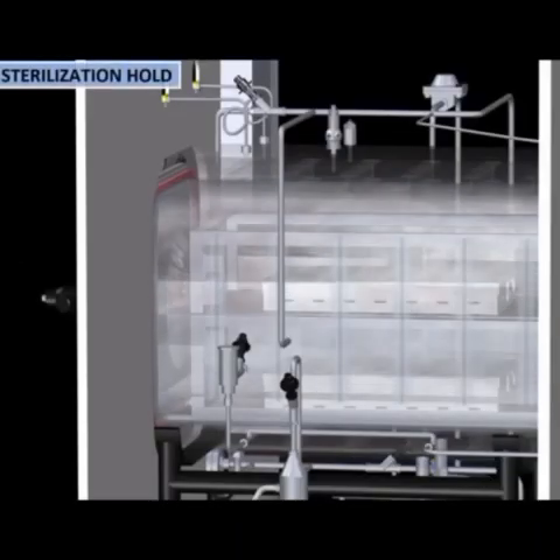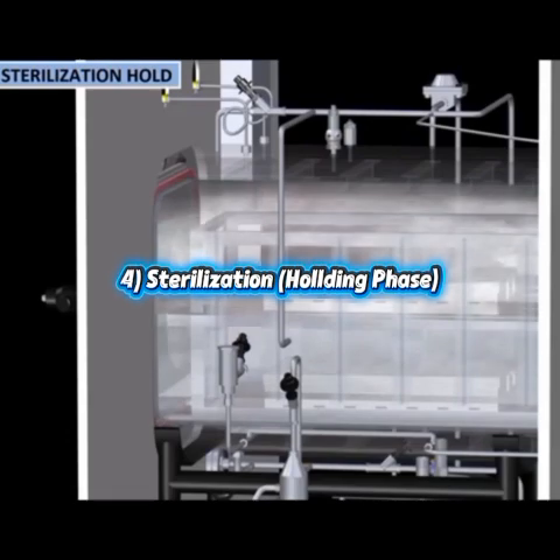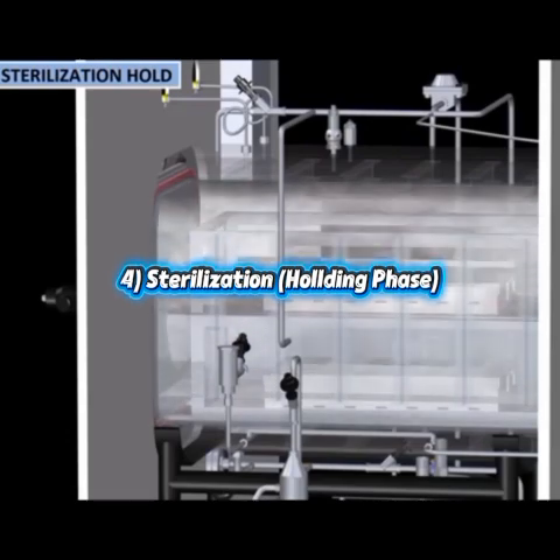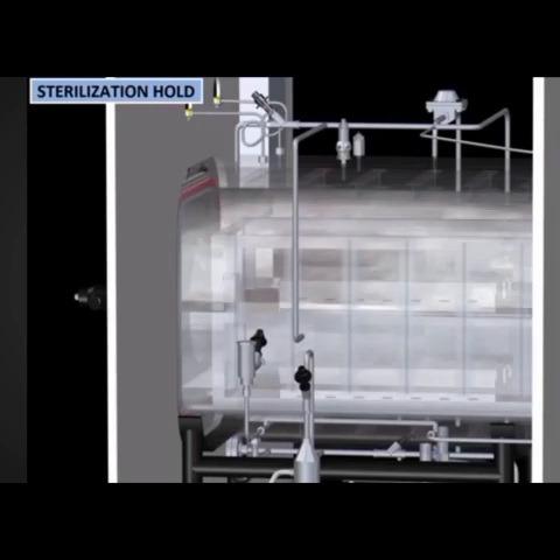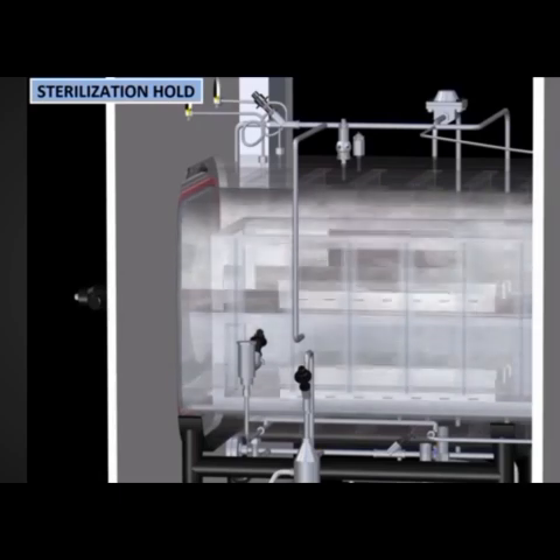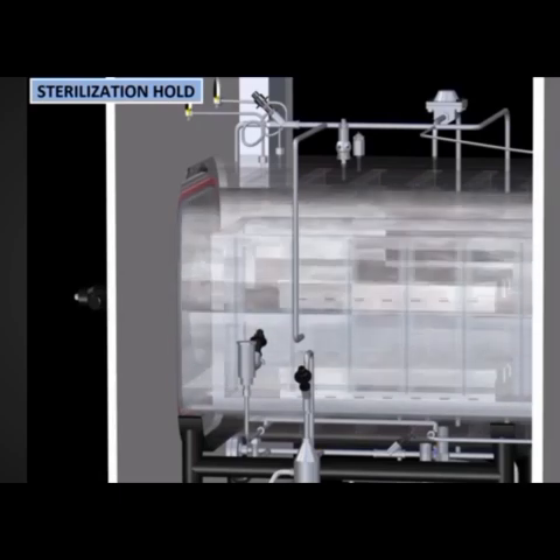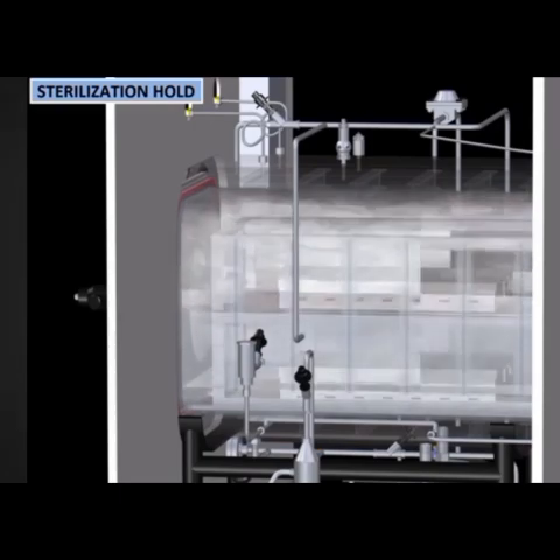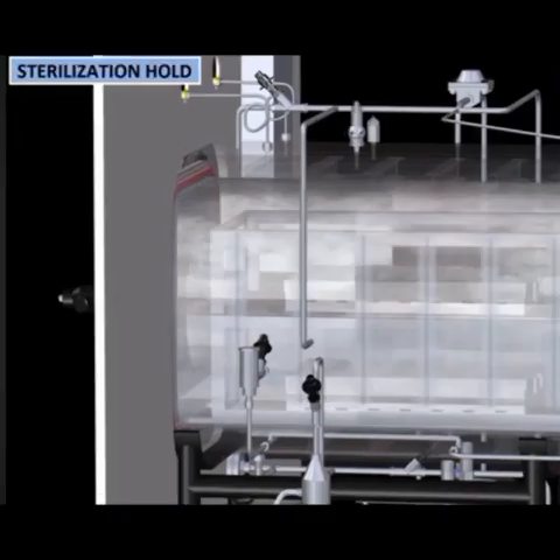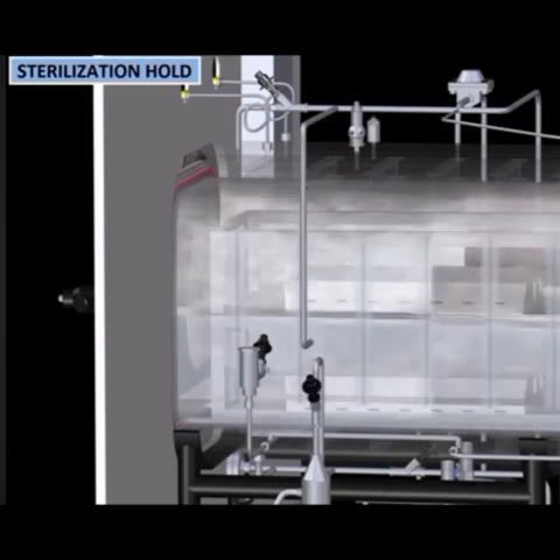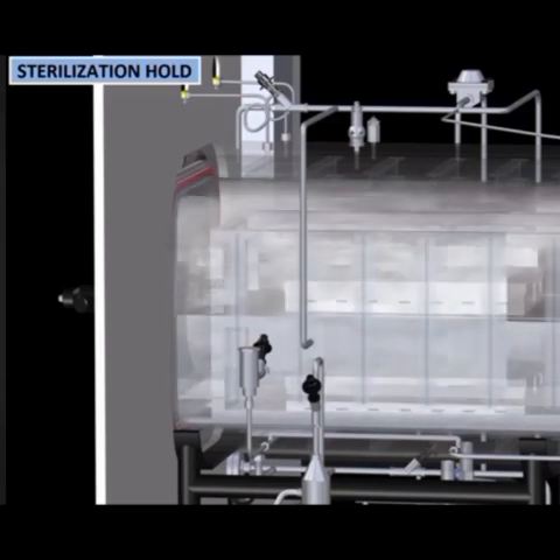The fourth step is called sterilization, also called the holding phase. The chamber reaches the required temperature and pressure, usually between 121 degrees Celsius and 134 degrees Celsius. During this holding time, heat and pressure effectively destroy bacteria, viruses, fungi, and spores.